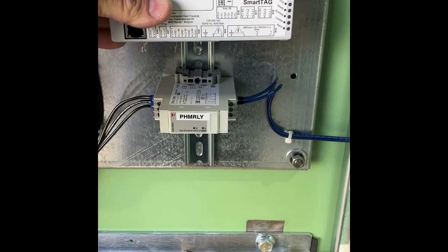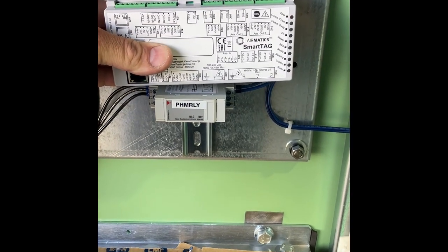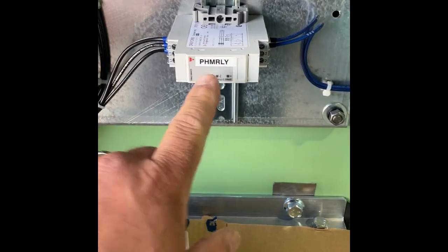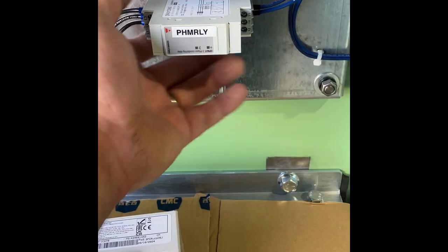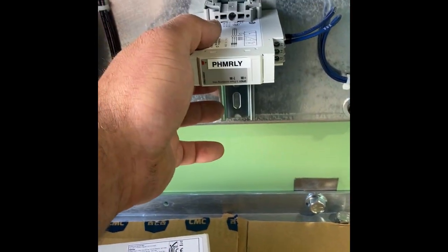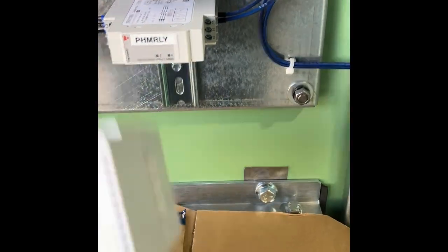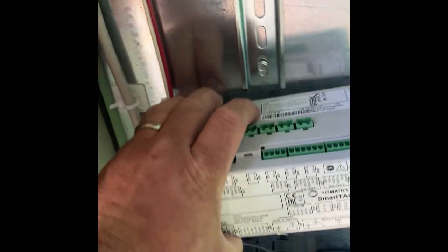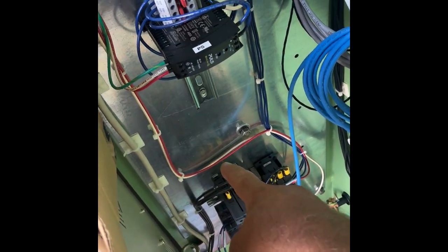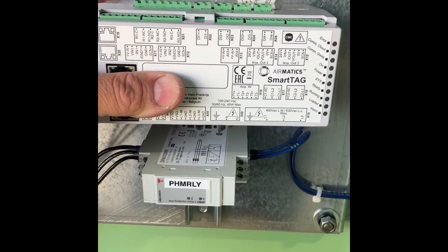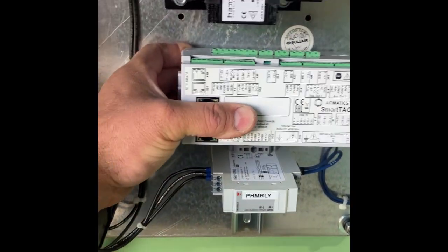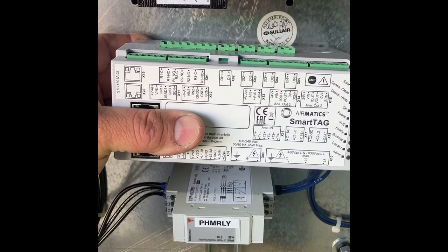Adequate spacing away from the control power transformer and adequate spacing away from my phase protection relay. But my phase relay is going to have to slide down. Actually, it's going to come off. I'm going to cut this DIN rail, and this relay is going to slide down to make room for this guy. I could put some DIN rail down here, but all my connections are going to be here and over here, so it doesn't make sense to have it all the way down there. Also, for initial status monitoring and troubleshooting, it's easier to have this thing right up here at about eye level. So yeah, I'm going to do that.